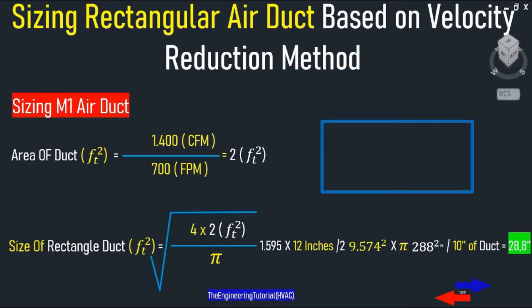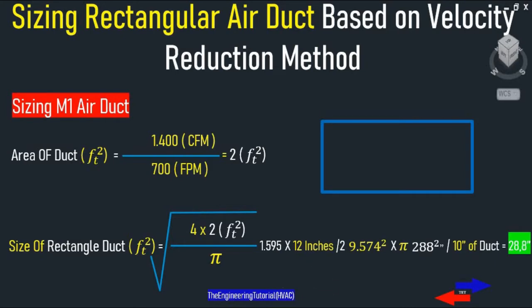So 288 square inches can be divided by the height or width of the main supply duct based on your needs. You can determine how many inches the height of your duct needs to be. For example, if we want the height of our main supply duct to be 10 inches, we simply divide 288 square inches by 10 inches, which gives us 28.8 inches width. So the duct size is 28.8 by 10 inches.